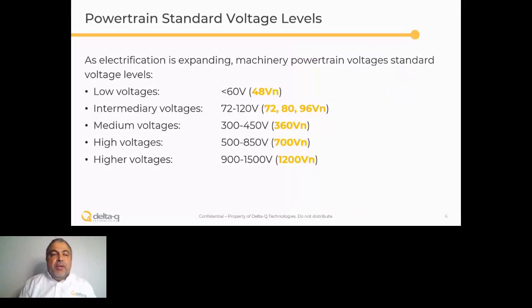This is just a reminder that there are some standard voltages when it comes to electrification. These voltages fall into 5 categories. What's known as the low voltages, those are voltages below 60 volts. Typically, it's a 48 volt nominal. Then there are what we call intermediate voltages. This includes 72, 80, and 96 volt nominal.